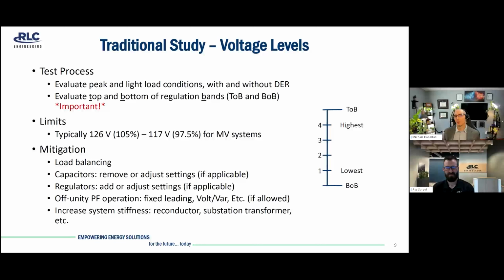So why it's important to look at the top and bottom of your regulation band is if you look at the simple graphic over here on the right side, this is kind of portraying a voltage regulation band of an LTC or a voltage regulator. You have a number of tap positions that's falling inside of your voltage regulation band. And when you run a simulation, that load flow simulation is going to find one of those tap positions that falls within your regulation band. But it doesn't necessarily dictate which one of those it's going to hit. So under normal load flow operation, maybe it lands on 2, maybe it lands on 3.